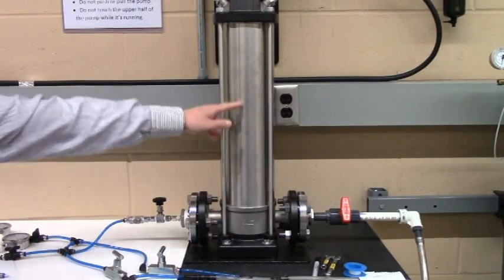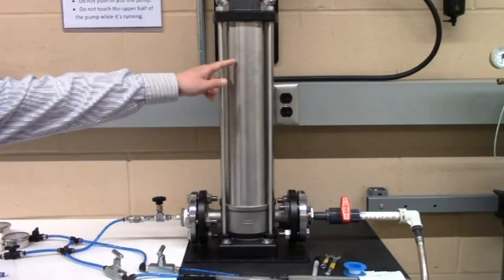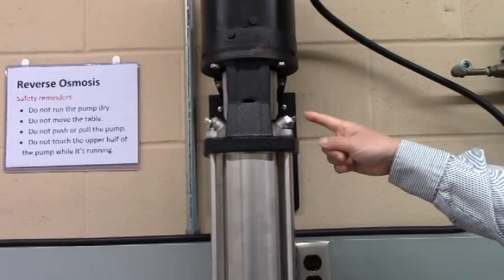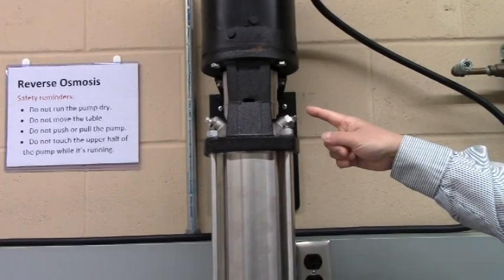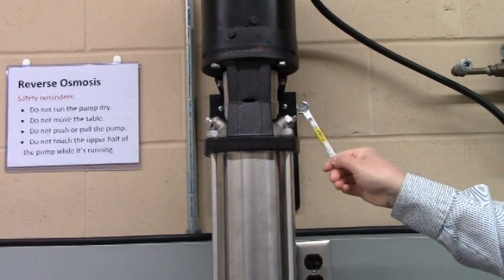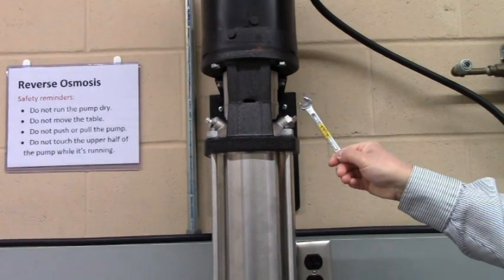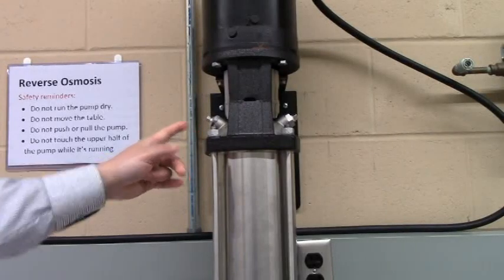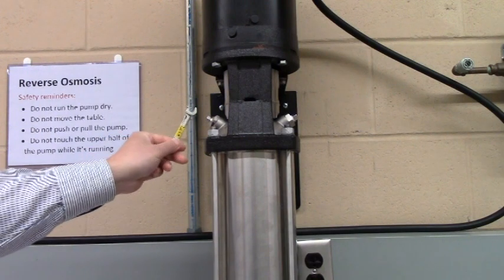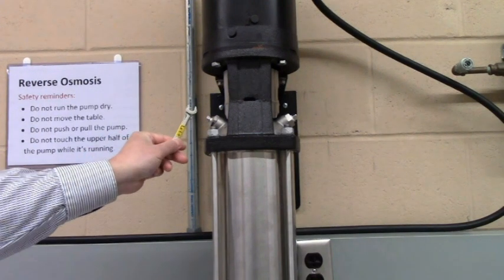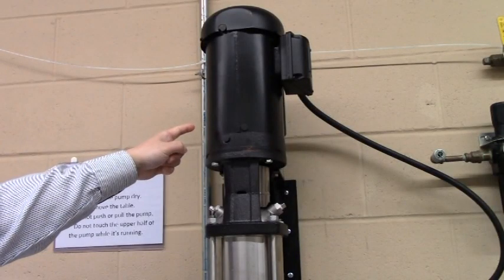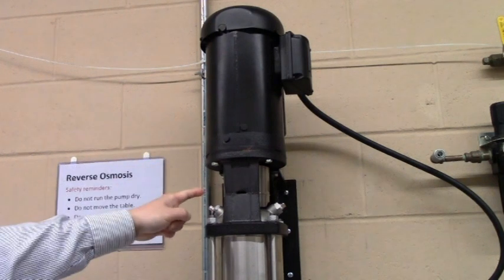The vertical centrifugal pump has multiple impellers in the column to deliver high pressure. Pump's prime inlet is located at the upper right side, and you need a wrench to open the screw. The pump's prime outlet is located at the upper left side, and you need another smaller wrench to open the screw. At the top of the pump is a motor in the black housing.